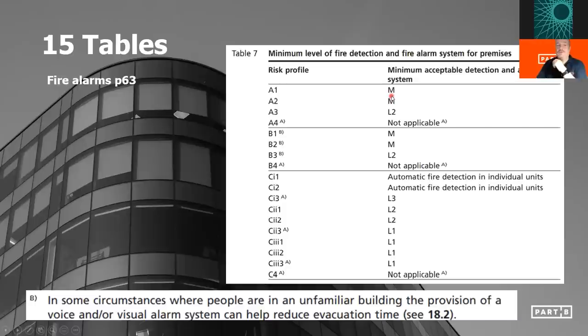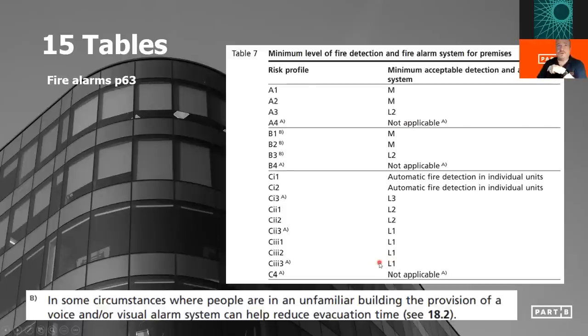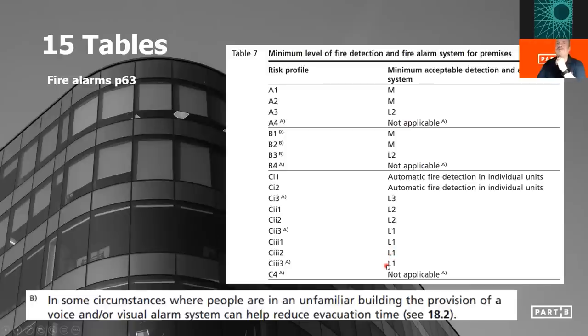Table 7 states minimum acceptable detection alarm system — so for an A1 building, if you want to put an L3 or L2 or L1 system in, go ahead — you will get a benefit for it. When we look at C buildings where people are likely to be asleep — hotels in BS9999 — it requires an L1 system. The general fire safety guides recommend an L2, and I believe ADB is also happy with an L2. So BS9999, while it gives you benefits, actually ups the protection levels expected for a sleeping risk compared to what you'd expect to see elsewhere.